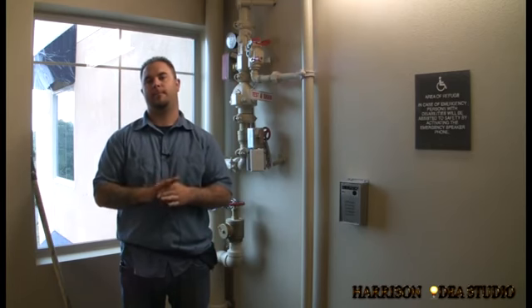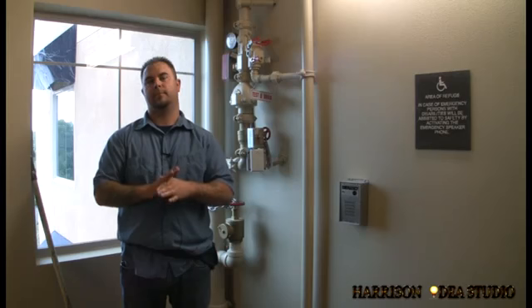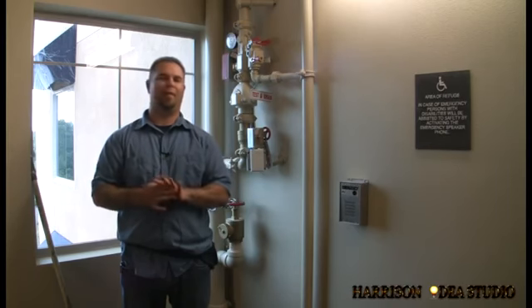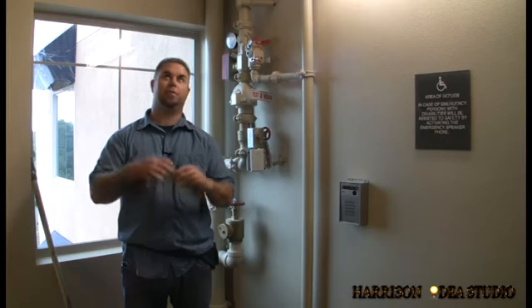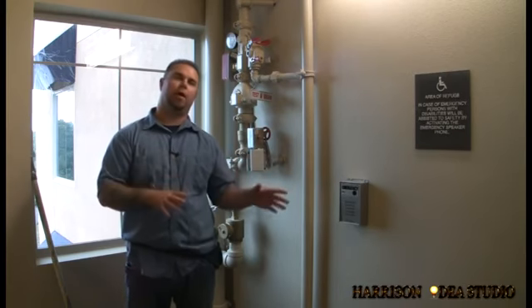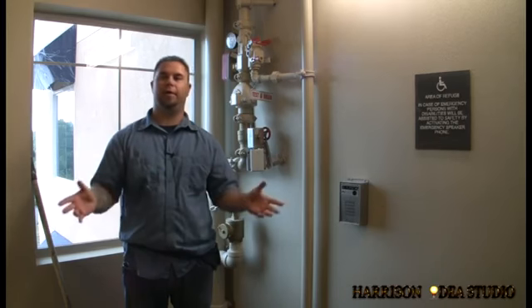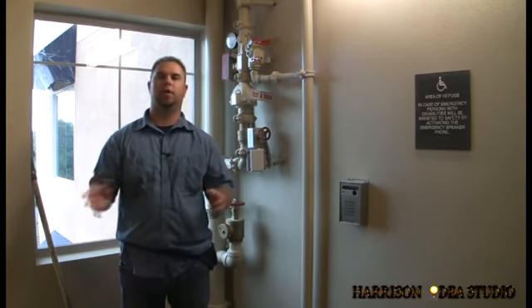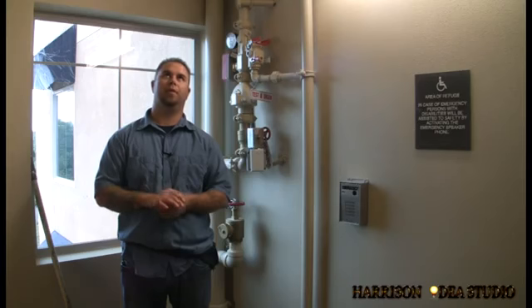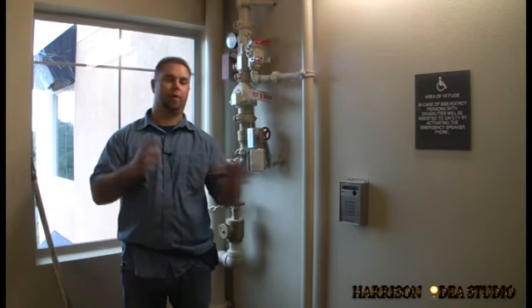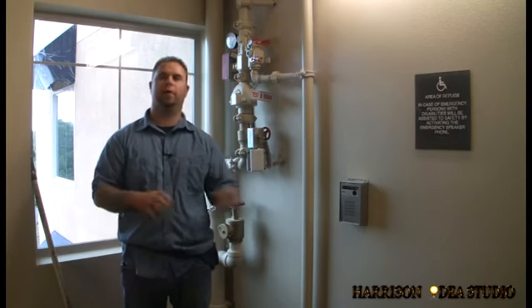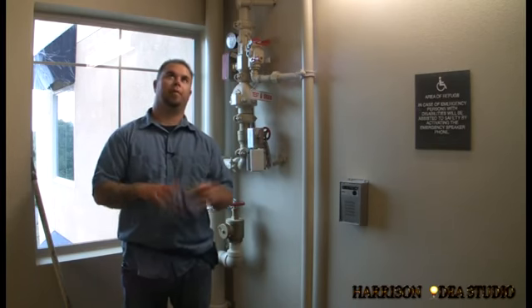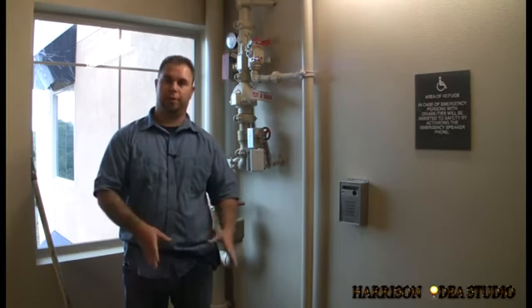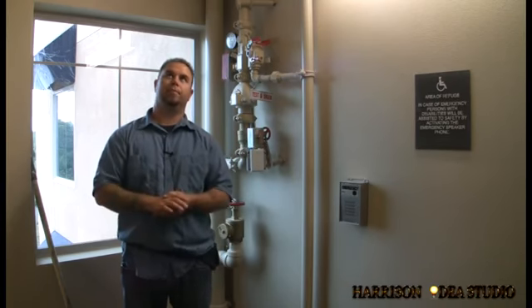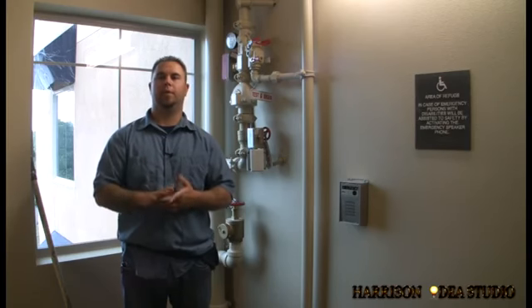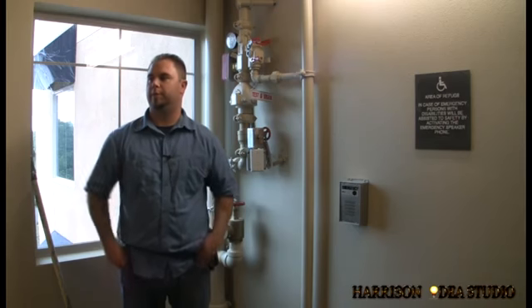Is there any reason for them to call the monitoring company to say this is a false alarm? Because the trucks will roll no matter what. Yeah, by the time you can get it figured out and shut it all off, and the fire department's going to be here, they'll notify the monitoring company that it was a false alarm. Okay. Yeah, there's no phone calls that need to be made. You just want to let the fire department know it's a false alarm. They'll come up, check it out. Sometimes the fire department will replace the sprinkler with the spare sprinklers that are downstairs. A lot of times you'll have to call us out to come back and put in a new sprinkler. And then we can re-energize the system and put it back online.